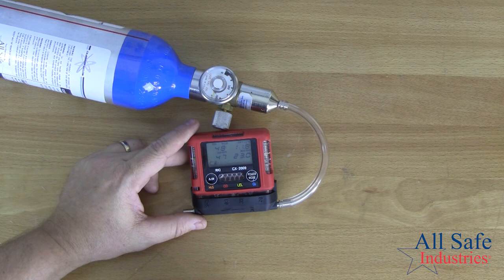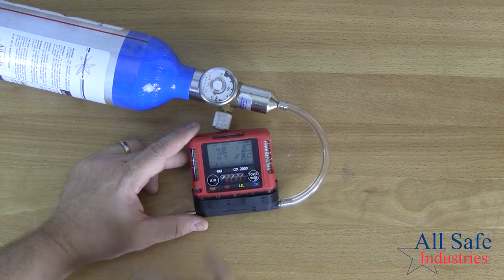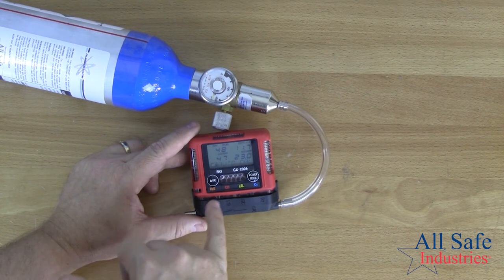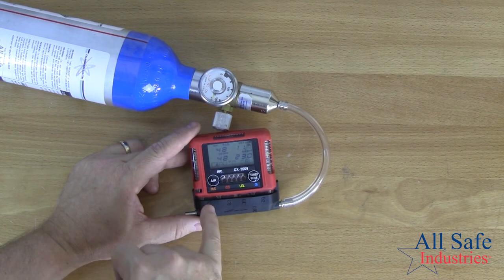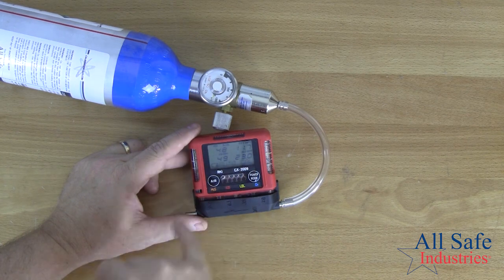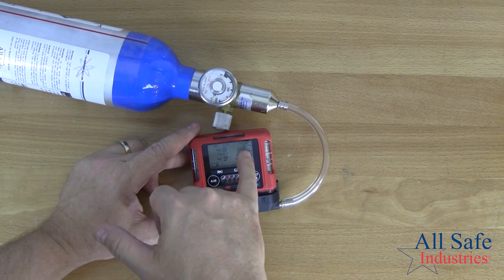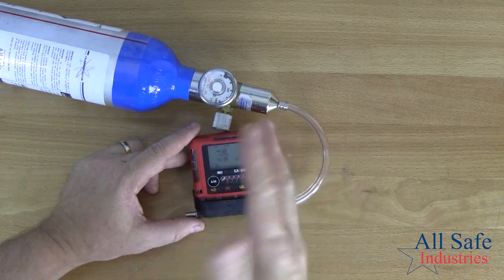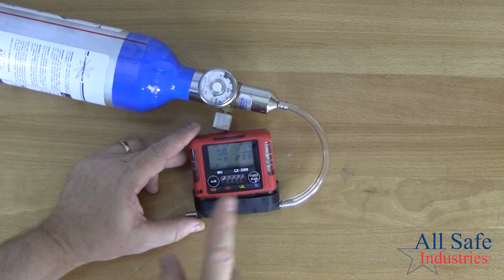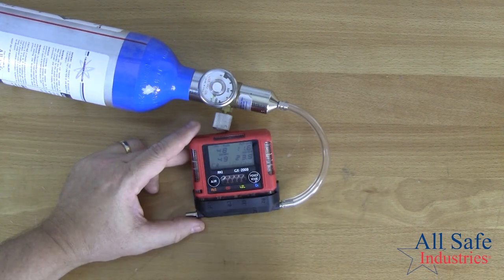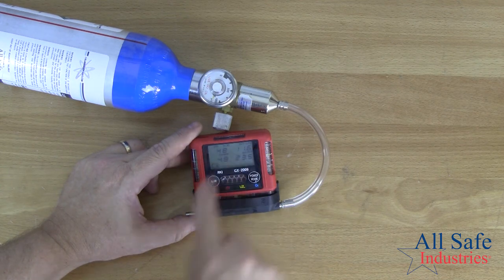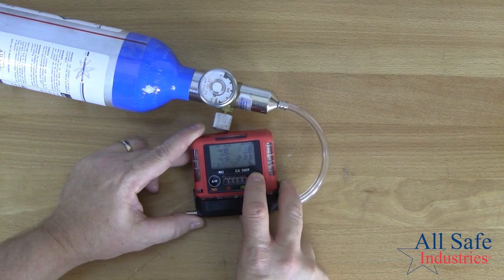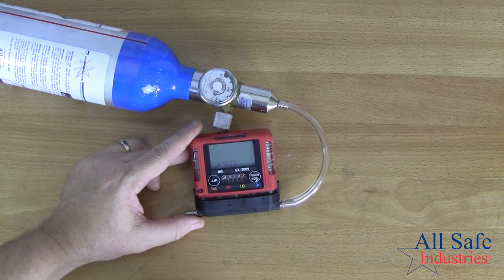We'll automatically reset the sensors to the calibration gas that we're using. That's why we want to use the right gas. And so I'm seeing my LEL has stopped moving. My CO is right where it needs to be. My H2S is close. And my oxygen sensor. When you press the cal button, it's going to reset these numbers to the right values. So now that the numbers have stopped moving, I'm going to press power mode. It says pass.